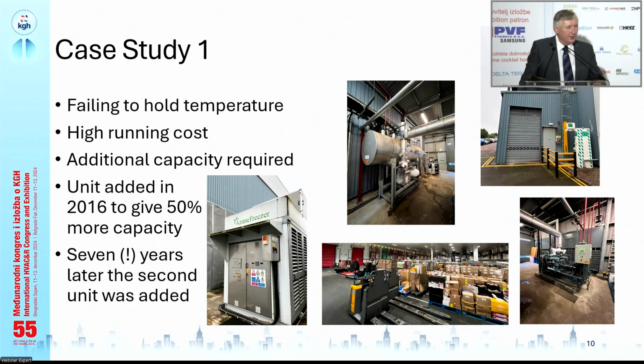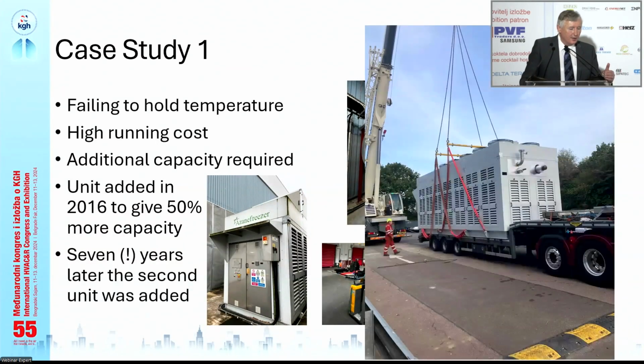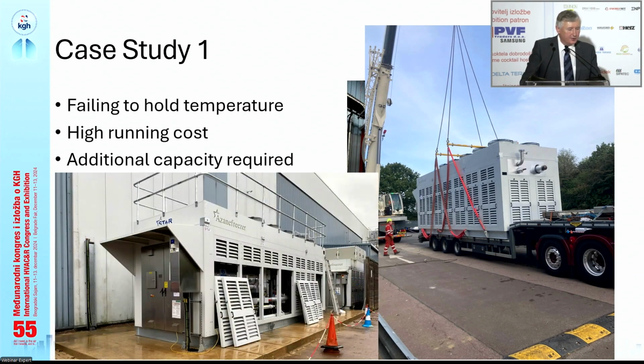So there was clearly something wrong with the plant that the customer was generally satisfied with. 7 years later, they came back and we stripped out the old plant and we delivered a second unit, which now enabled them to run the plant on full load without using the old pump system. So what benefits did they get from that? Here you can see the second unit installed beside the first one. No plant room here. This is all outside the building. The only connections inside the building are welded steel pipes to the evaporators. No valves, no flanges, no screwed fittings at all. No chance of ammonia leakage inside the building.